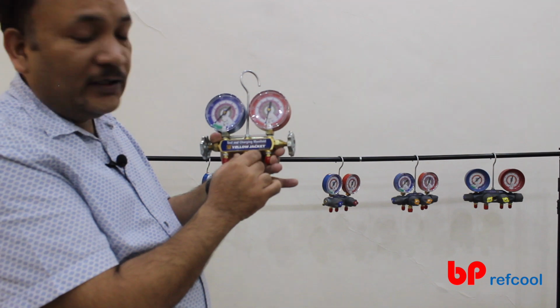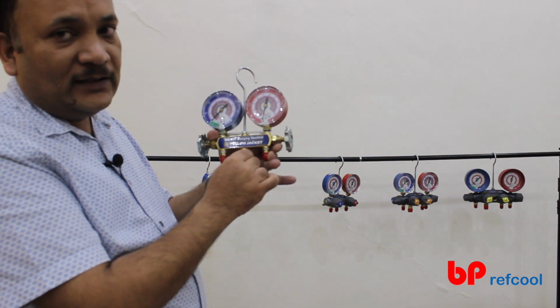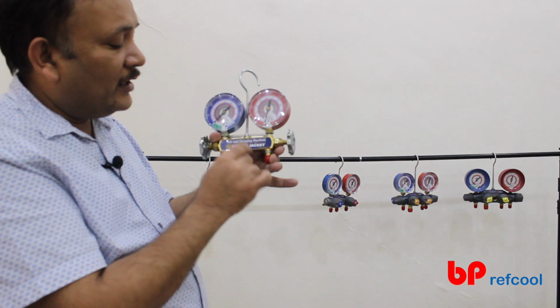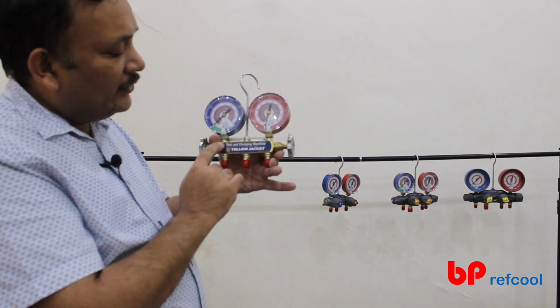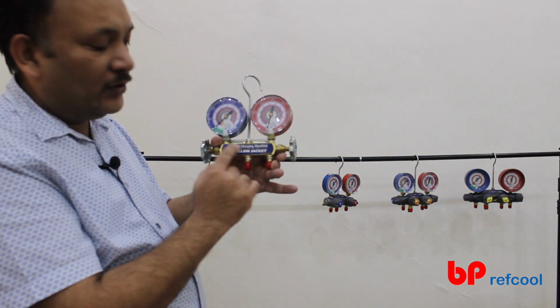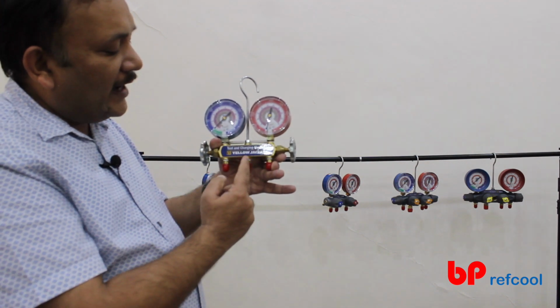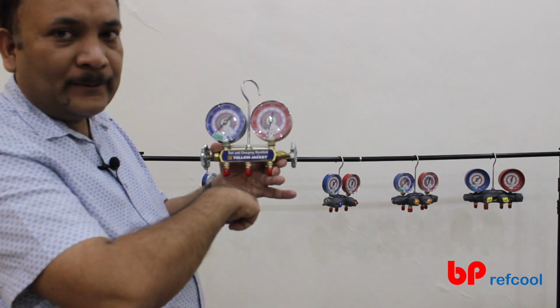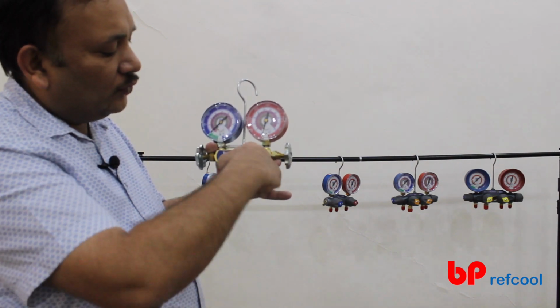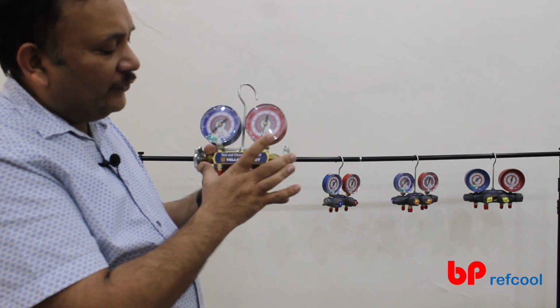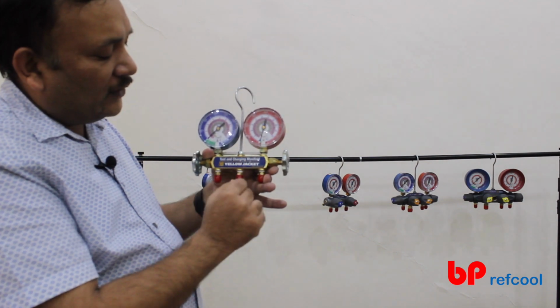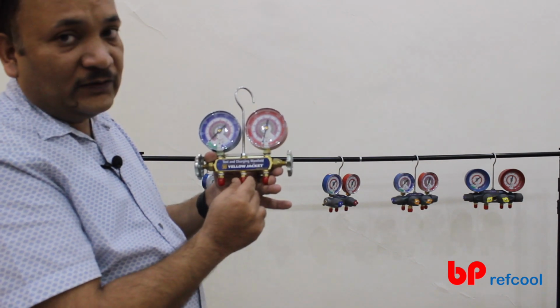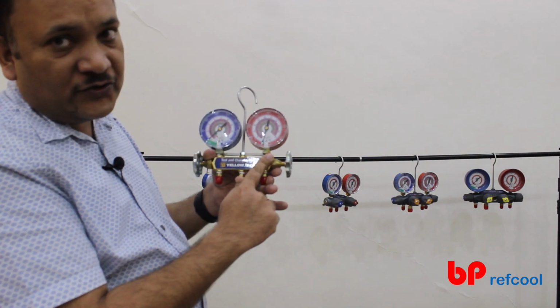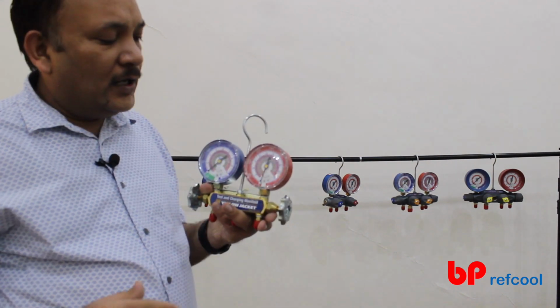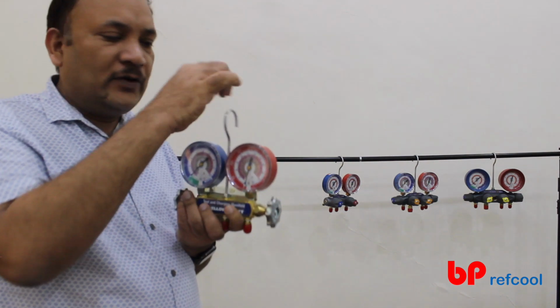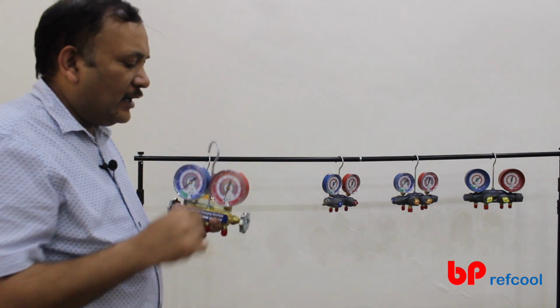For this connection, which is either for vacuum or for gas charging, you can use this valve to make or break the connection. If you open this, the gas or the vacuum will flow this way, and once you open this, it will also operate this way. These two are to manage the connections of this center hose, which you can connect to the suction side or to the discharge side. So this is a typical manifold gauge. Normally all these manifold gauges come with a steel hook so that you can hang them.